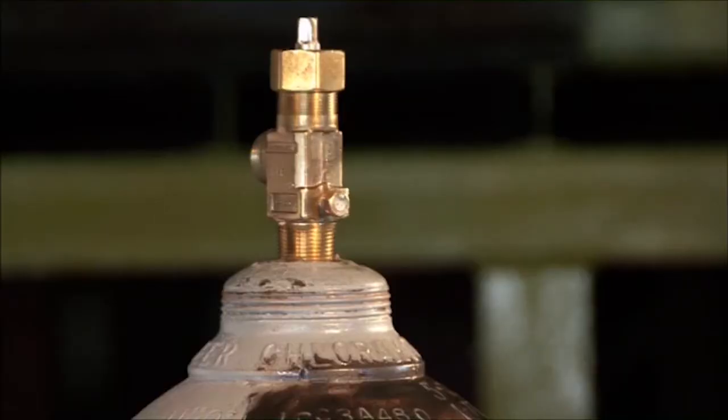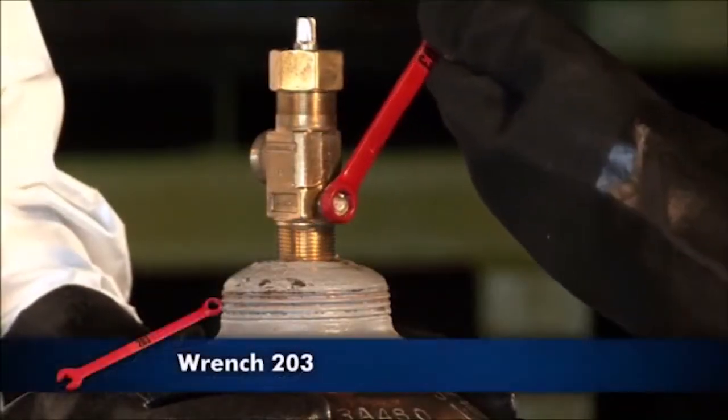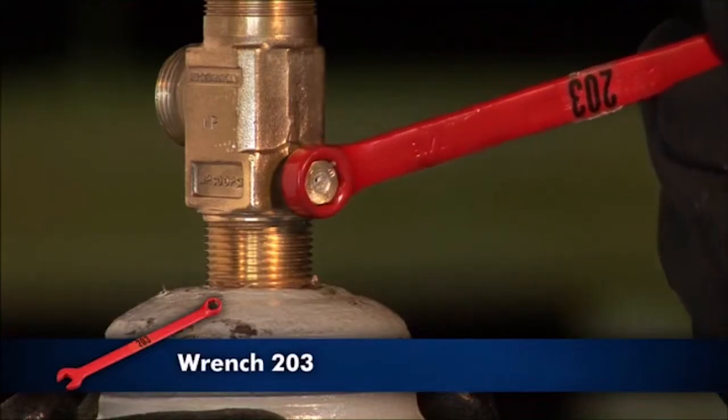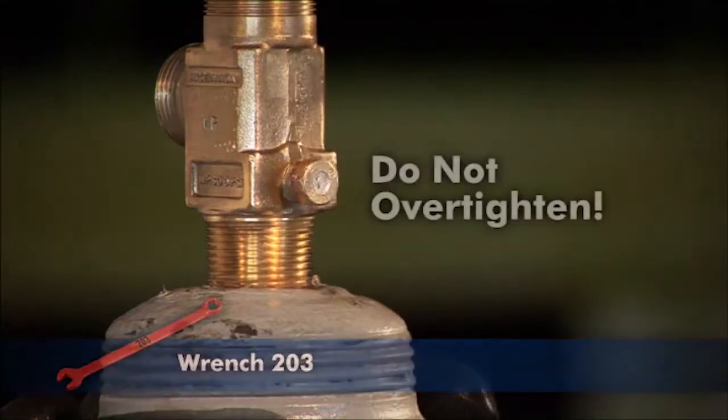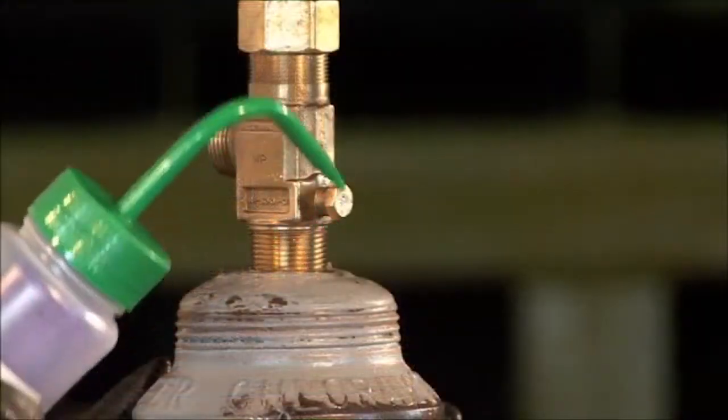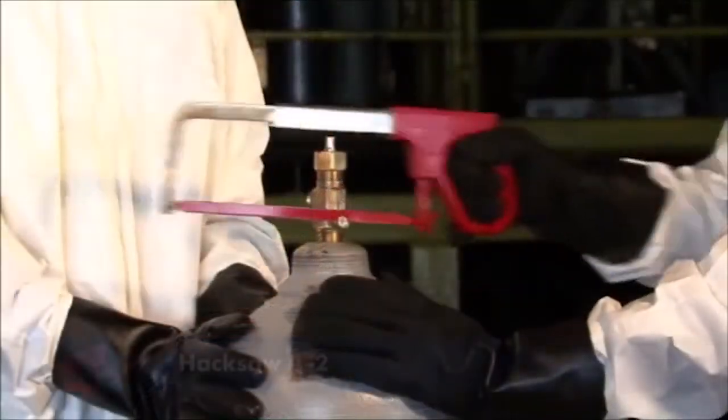If the leak is at the threads of the fusible plug, use wrench 203 and tighten the fusible plug slowly. Do not over-tighten. Test for leaks.